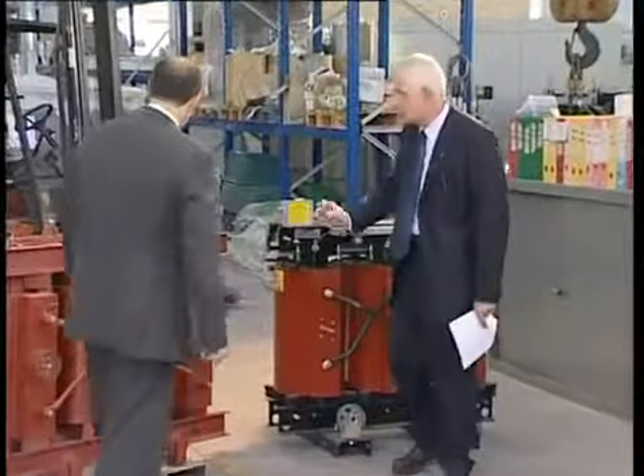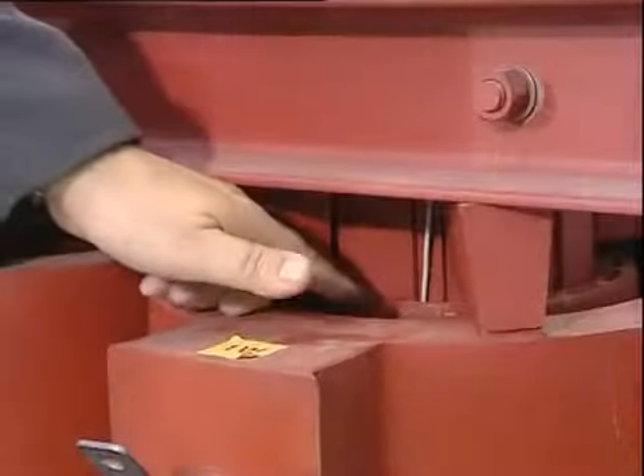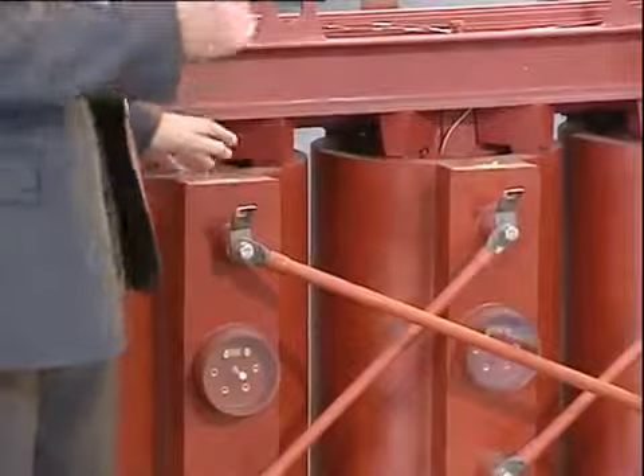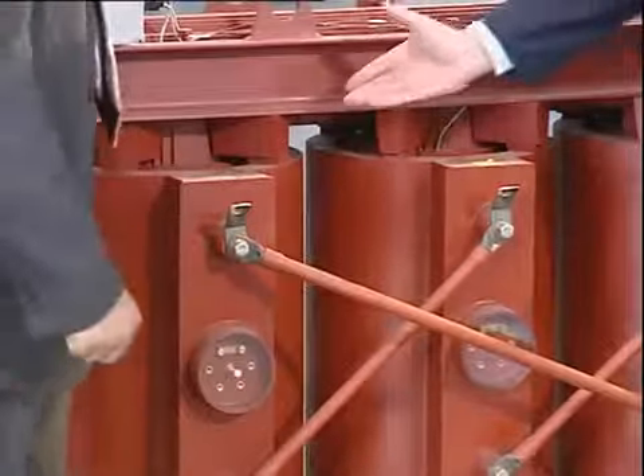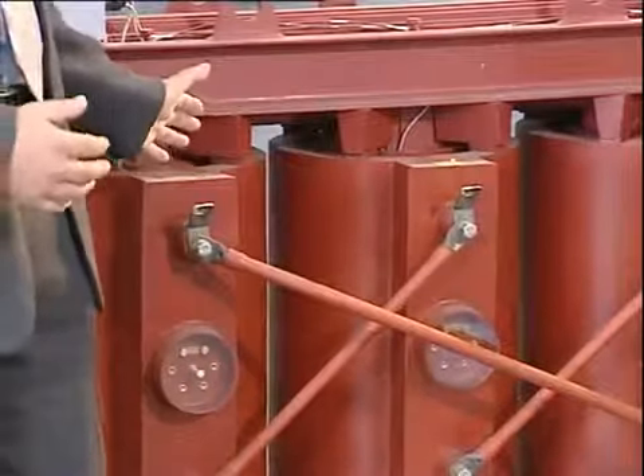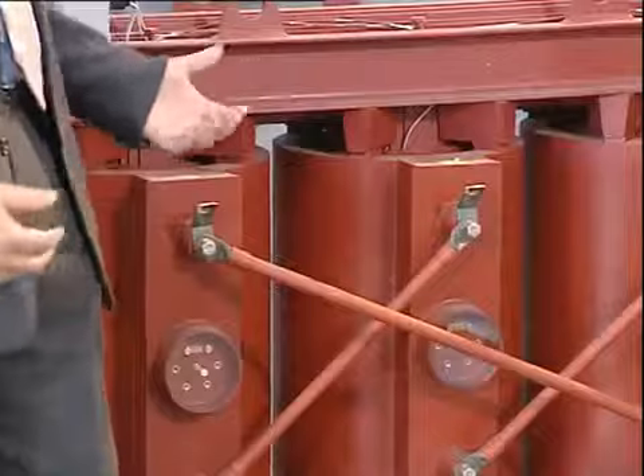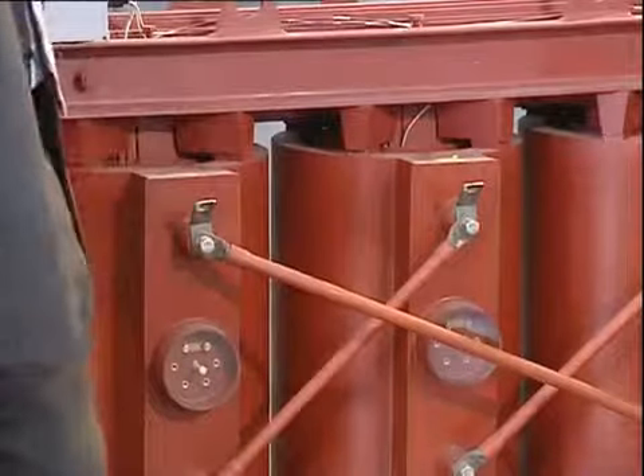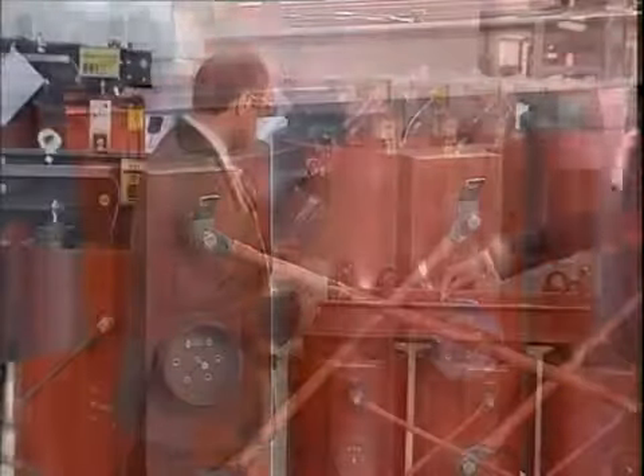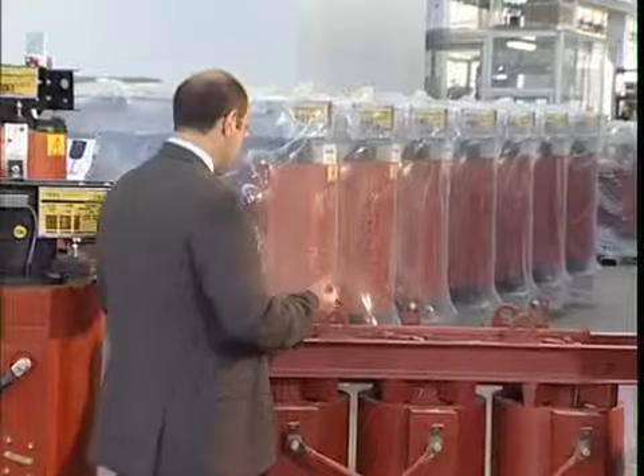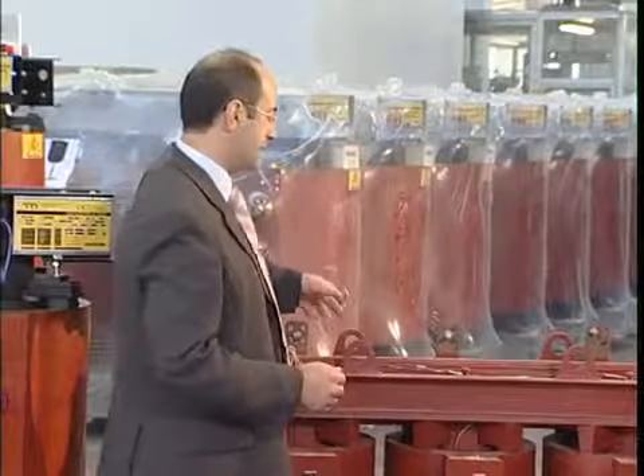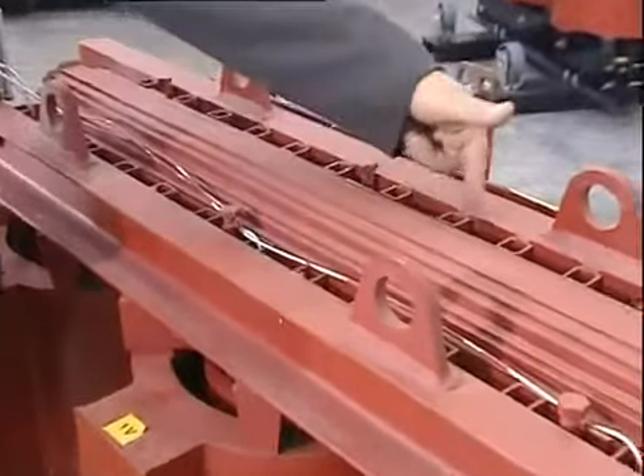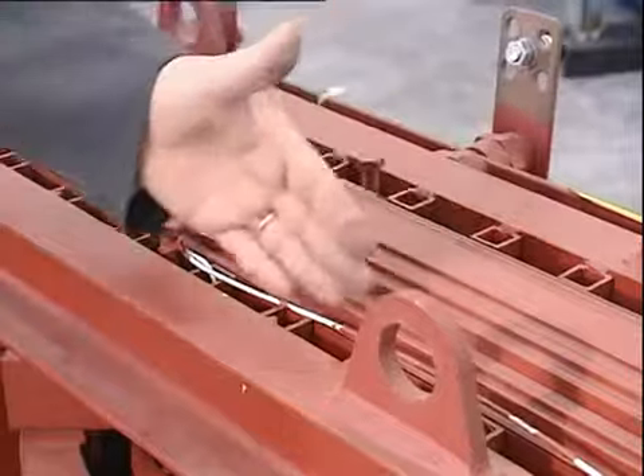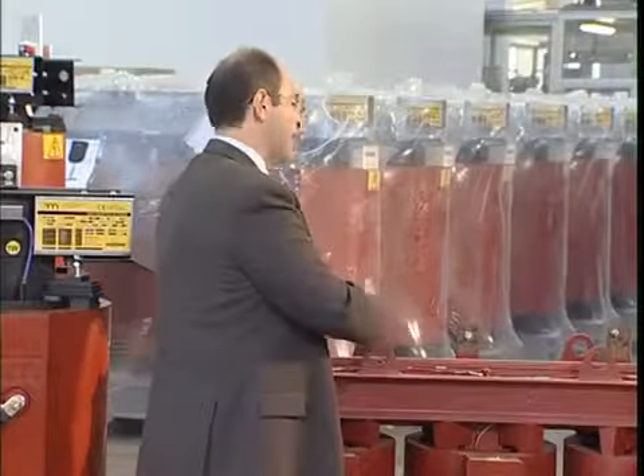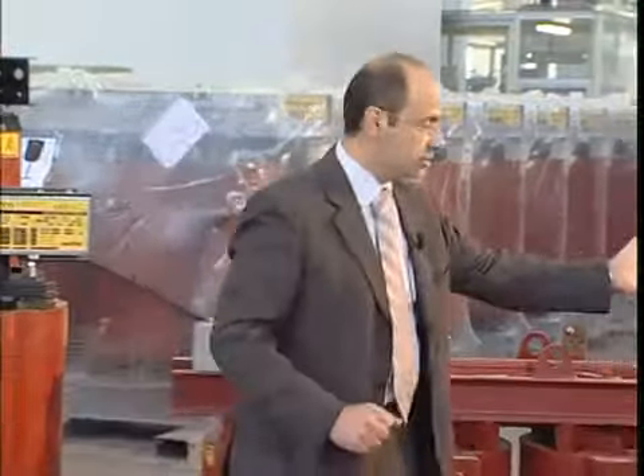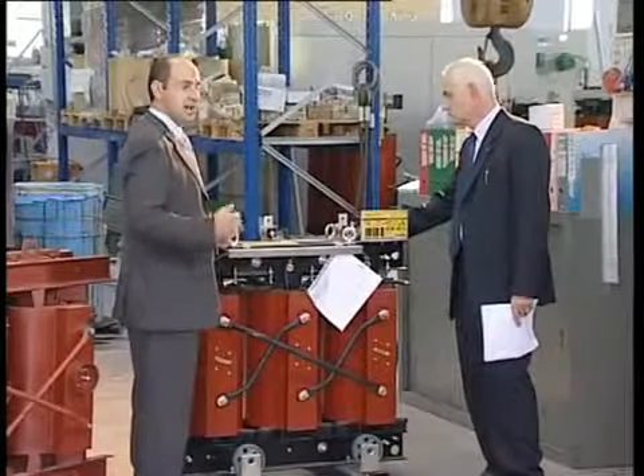What about this transformer in terms of cooling? Let's see. We can immediately notice that inside it, the cooling duct size is much less than half that of our transformers. Therefore, in case of dust build-up, they will clog. For sure, after a few years of operation, some dust will build up, which will probably clog the cooling ducts almost completely. Okay, regarding the windings, here I can see many cooling ducts. Contrary to what I expected, I see a considerable cooling surface near the core. And why is that? I would say that poor quality, high-loss ferromagnetic material has probably been used, requiring a large cooling surface, while our transformer has been manufactured using high permeability and low-loss laminations.